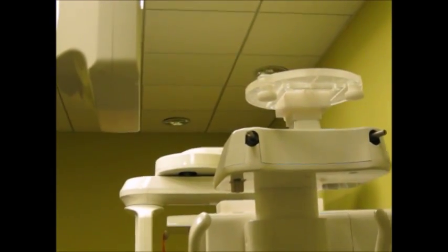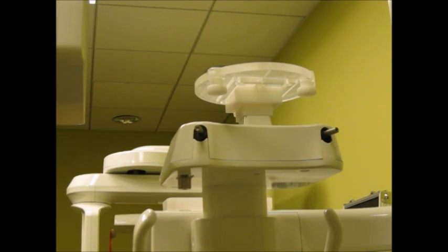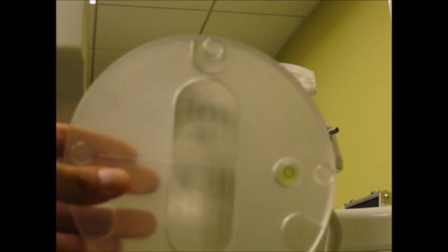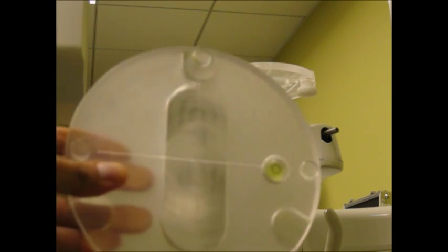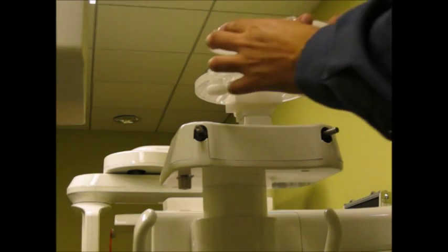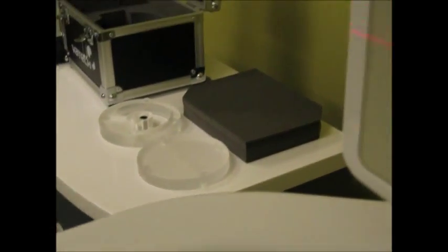Next, you have to place the second phantom on top of the jig. This second phantom is the level phantom, and is identified with the number 1, as you can see right here. The jig was identified with number 0, okay, and the level is identified with number 1. You can see that the level has this level tool, okay, it's a bubble, and the whole purpose of this piece is just to make sure that your kit is properly leveled on top of the chin rest.